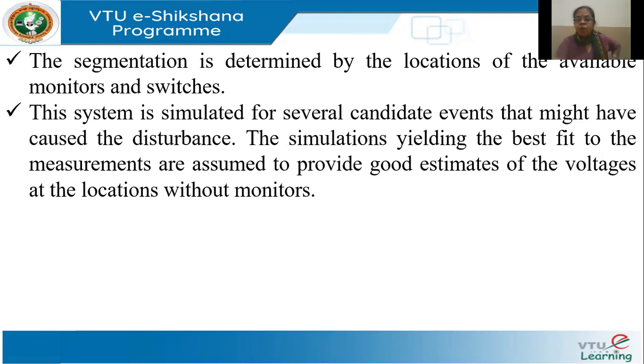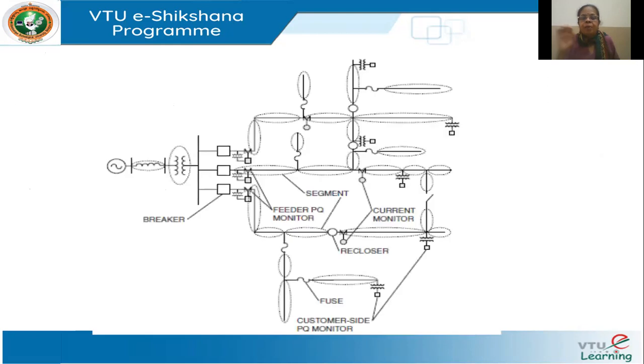Once we know an event has occurred, an event is when a deviation, a power quality problem has occurred, this model, it's a simulation actually, will try to simulate different events that might have caused the disturbance. For example, a sag has occurred. So why did this sag occur? I try to simulate suddenly an overload, or a sudden motor starting, or a single line to ground fault. Whichever gives the best results, we take that as the cause of the disturbance and those estimates as authentic. Clear? So these are some of the issues involved in estimation.